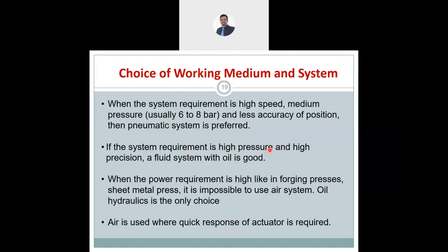If the system requirement is high pressure, maybe up to 100 bar, and high precision, then a fluid system with oil, a hydraulic system, because it uses oil, will be good. As I told you earlier, you use pneumatic when you need high speed and low or medium pressure. If you want high pressure and slower speed or high precision, these are the keywords for hydraulic. High pressure, high precision, very accurate. So you use a hydraulic system.